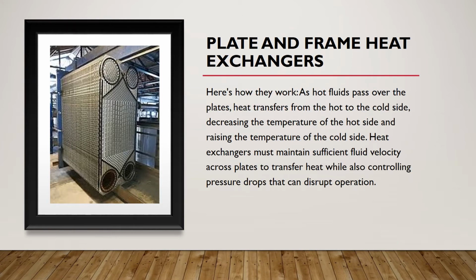Here's how they work. As hot fluids pass over the plates, heat transfers from the hot to the cold side, decreasing the temperature of the hot side and raising the temperature of the cold side. Heat exchangers must maintain sufficient fluid velocity across the plates to transfer heat while also controlling pressure drops that can disrupt operation.